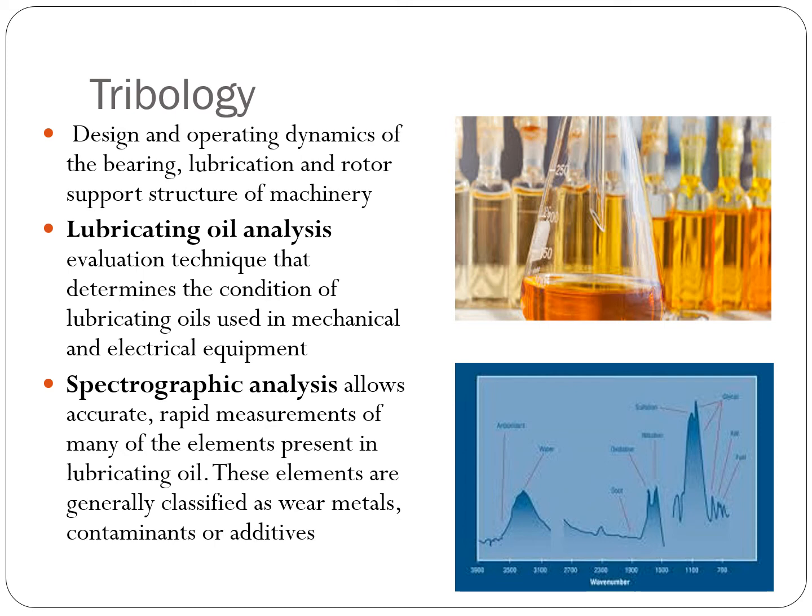that determines the condition of lubricating oils used in mechanical and electrical equipments. A comparison of the amount of trace metals in successive oil samples can indicate the wear patterns of oil-wetted parts in plant equipment, and it will provide an indication of machine failure. Using the scanning electron microscope on a carefully taken sample of debris suspended in the lubricating oil, the instrument then reveals the elements contained, their proportion, size, and morphology.